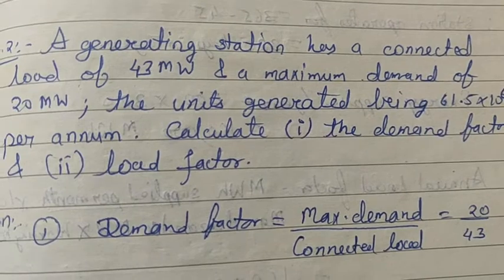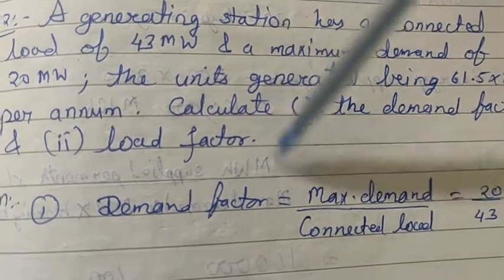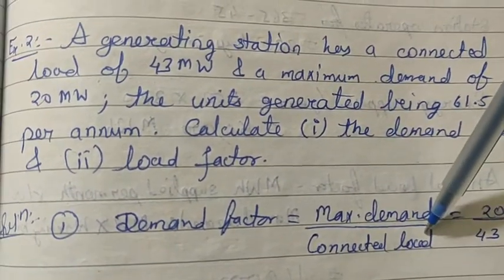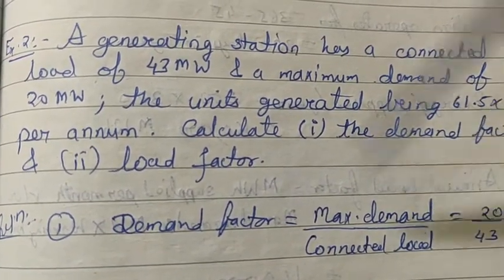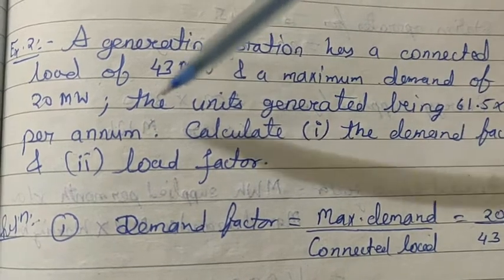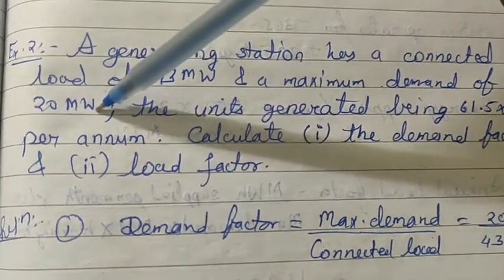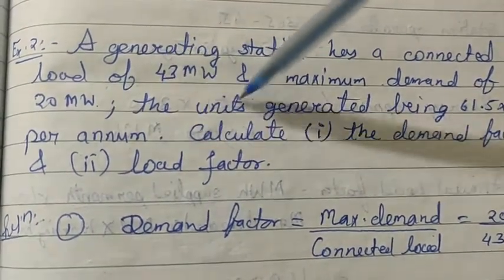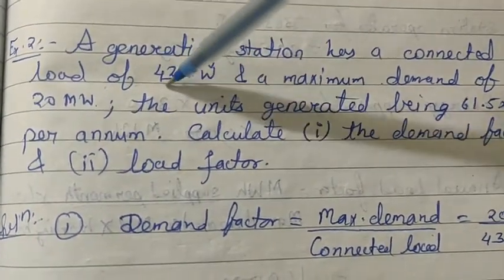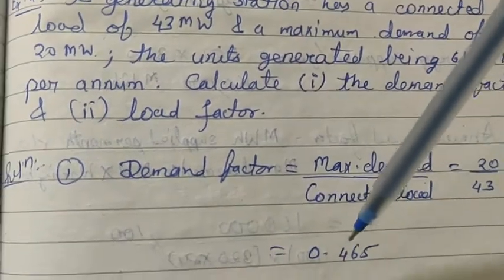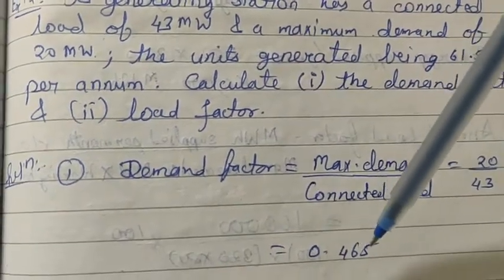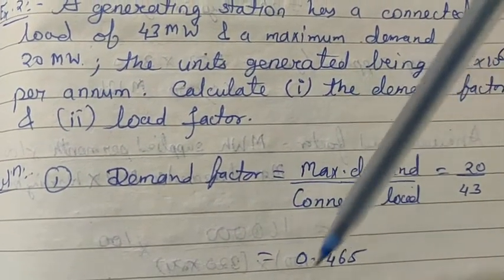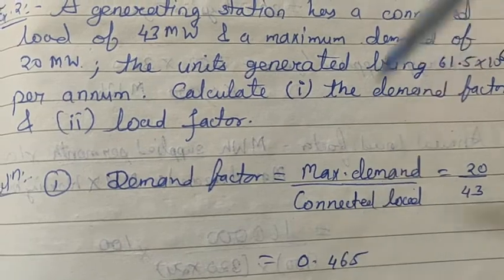The formula for demand factor is maximum demand divided by connected load. Maximum demand is 20 megawatt and connected load is 43 megawatt. So the demand factor comes out to be 0.465.